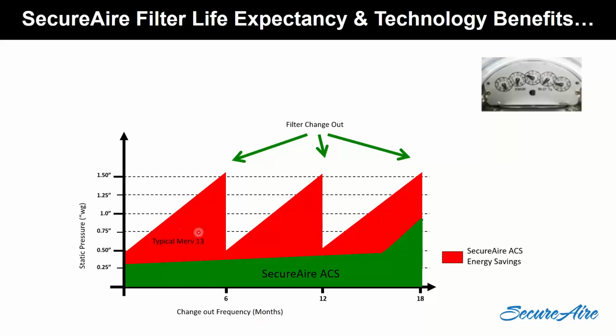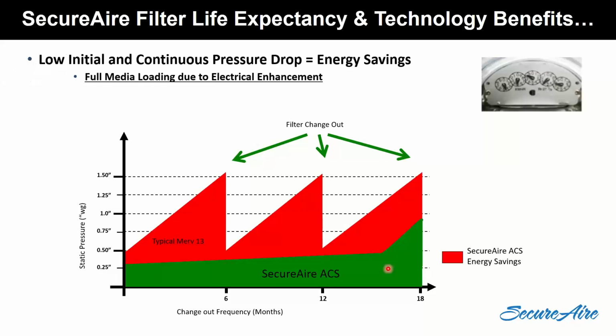So if you're already changing filters every 3 months, and then you put in a Merv 13, which catches more stuff, you'll have to change the filter more than every 3 months, right? Something like this technology, though, the SecureAire, it loads differently. Here's the airflow coming this way. Instead of loading on the face of the filter, it actually loads on the backside forward, so it's a little bit less restrictive. So as you can see in the green here, the pressure builds up slowly, and we can get a year and a half out of it before we have to change the filter. Filters cost more, right? So there's more cost that way, but there's a little bit less labor cost from the frequency of having to change them.